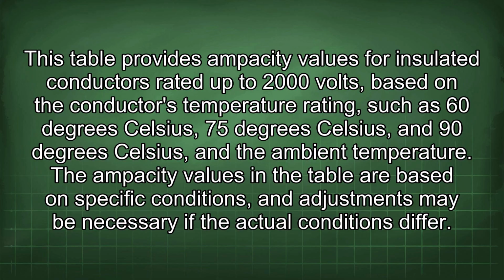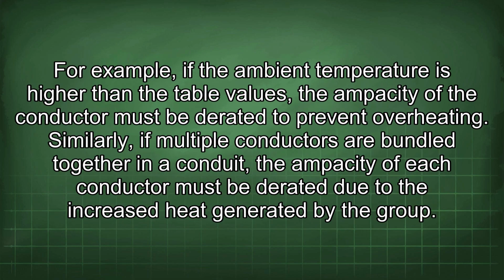The ampacity values in the table are based on specific conditions, and adjustments may be necessary if the actual conditions differ. For example, if the ambient temperature is higher than the table values, the ampacity of the conductor must be derated to prevent overheating. Similarly, if multiple conductors are bundled together in a conduit, the ampacity of each conductor must be derated due to the increased heat generated by the group.